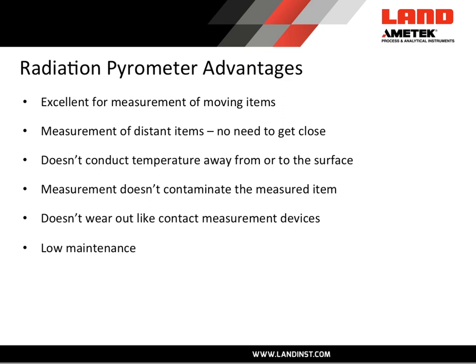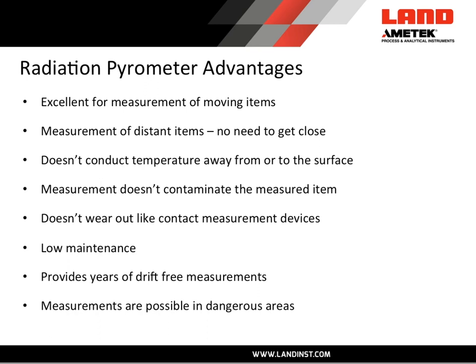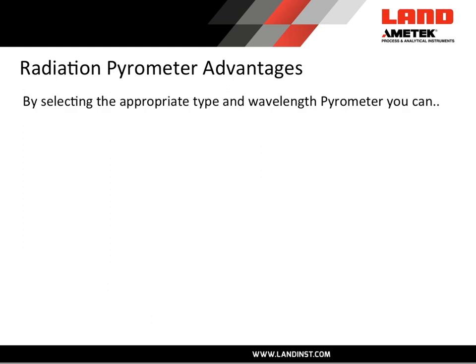Because of this, radiation pyrometers have very low maintenance even when making very high temperature measurements. There is no drift over time, unlike the thermocouple hot junction which can migrate. Measurements are possible in dangerous areas — if you want to measure something at high voltage, you just look at it with the pyrometer without getting close. The response speed is extremely fast, in milliseconds. By selecting the type and wavelength of the pyrometer you can do things that cannot be done by contact means.